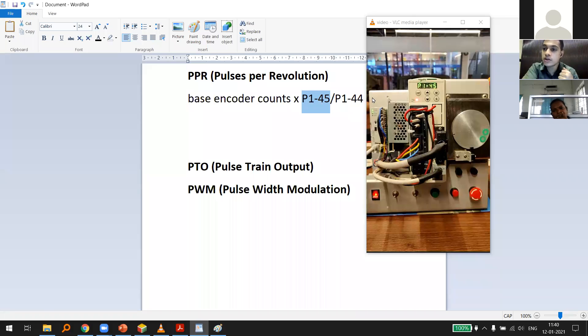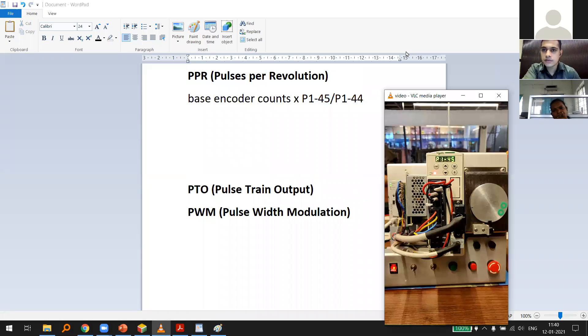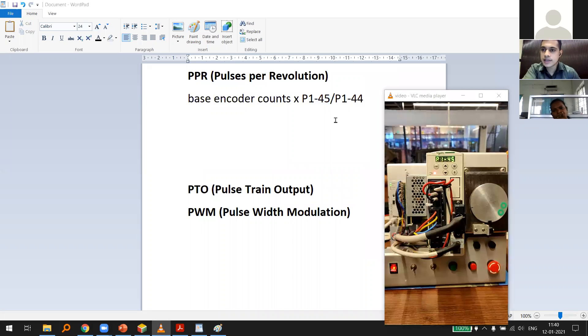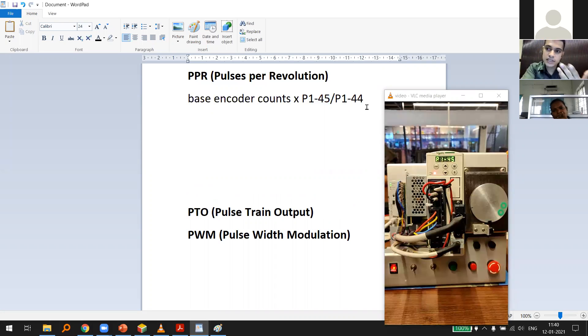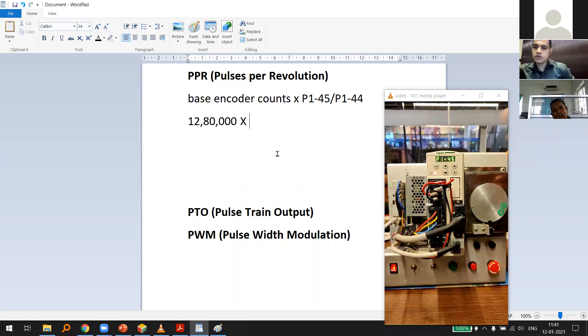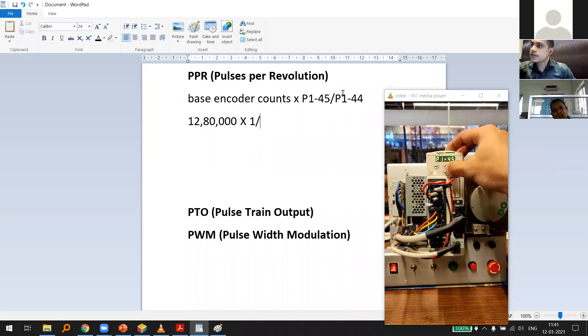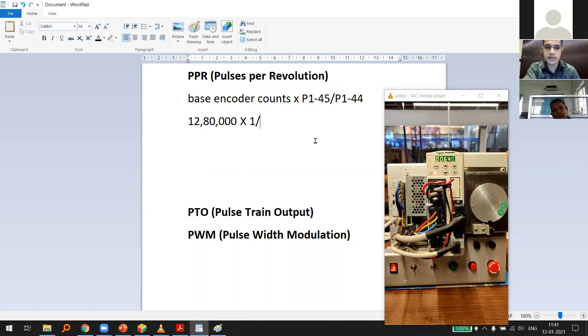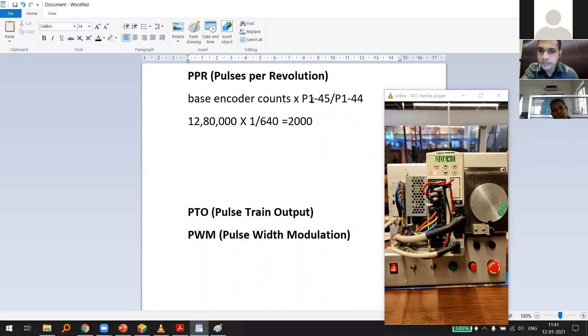P145 is the numerator and P144 is the denominator — we call this gearing. The base encoder PPR in this servo is 1,280,000 (12 lakh 80 thousand), which is fixed inside the servo. Multiplying by P145 (=1) and dividing by P144 (=640) gives 1,280,000 ÷ 640 = 2,000 pulses per revolution.